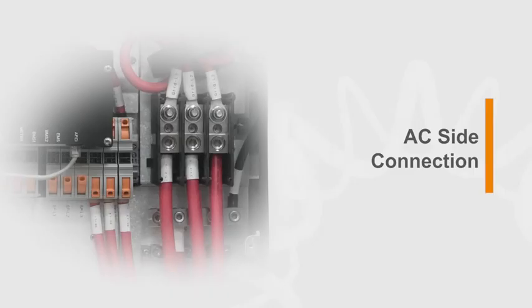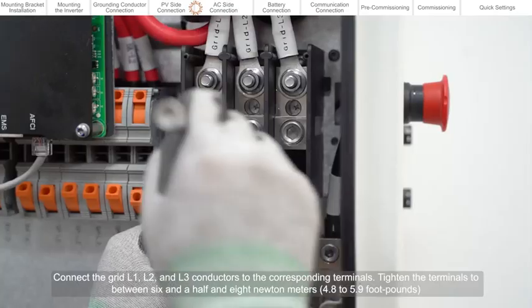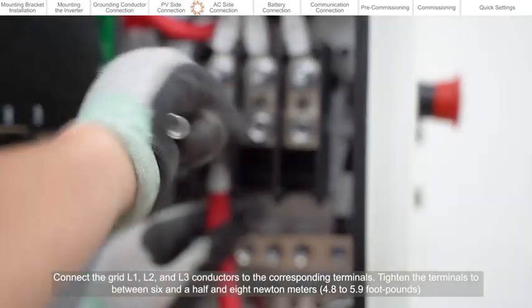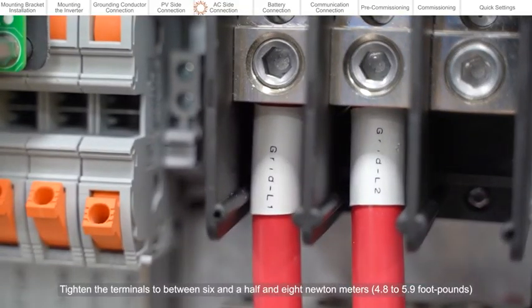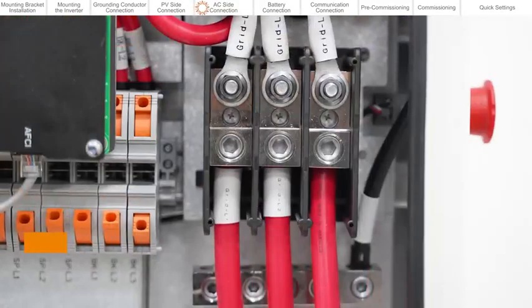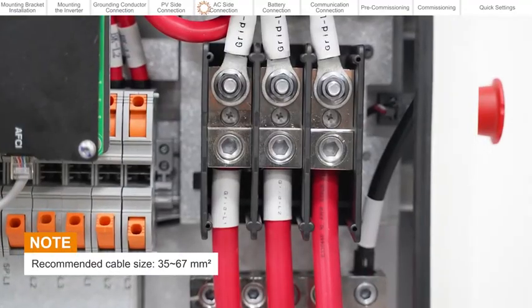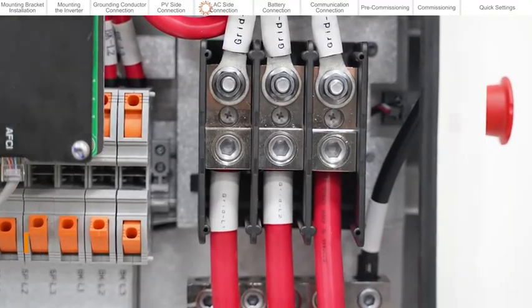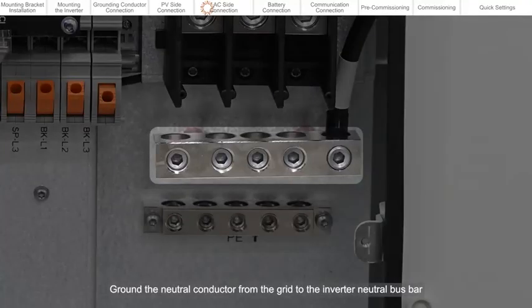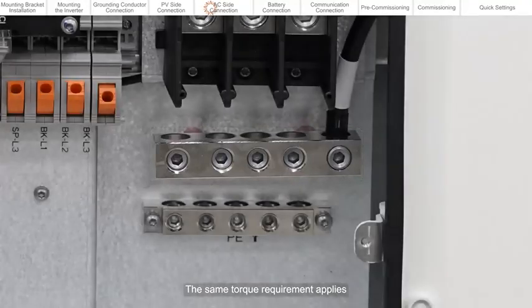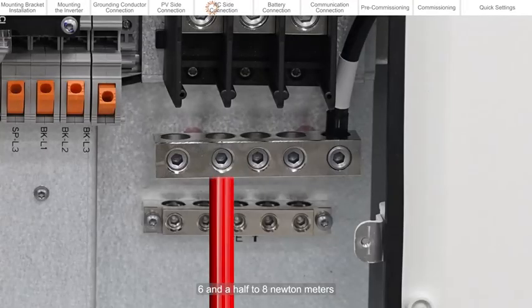AC side connection. Connect the grid L1, L2, and L3 conductors to the corresponding terminals. Tighten the terminals to between 6.5 and 8 Newton meters. Ground the neutral conductor from the grid to the inverter neutral bus bar. The same torque requirement applies, 6.5 to 8 Newton meters. Follow this same method for all of the other neutral conductors.